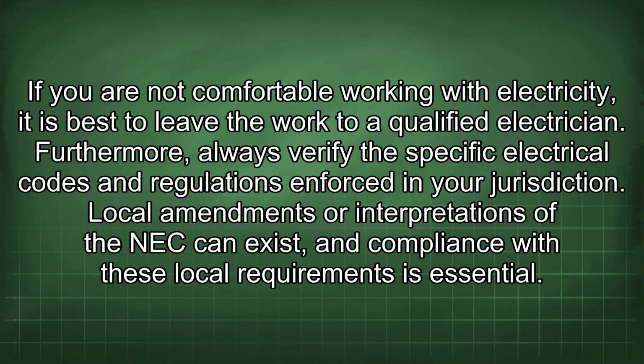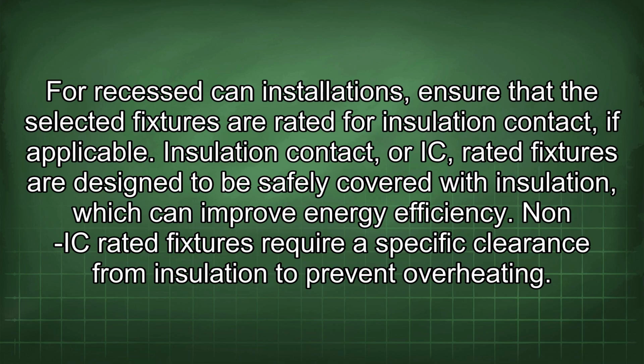Furthermore, always verify the specific electrical codes and regulations enforced in your jurisdiction. Local amendments or interpretations of the NEC can exist, and compliance with these local requirements is essential. For recessed installations, ensure that the selected fixtures are rated for insulation contact, if applicable. Insulation contact, or IC, rated fixtures are designed to be safely covered with insulation, which can improve energy efficiency. Non-IC rated fixtures require a specific clearance from insulation to prevent overheating.